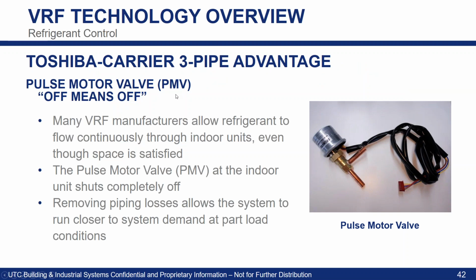So our refrigerant control, exclusive to Toshiba-Carrier. Each fan coil is going to have a PMV valve, or pulse motor valve. And you can see off means off, right? Quotations. There's a purpose why we have that. We are 100% closed on our PMV, okay? So if you guys can envision this, you have a heat recovery system and you have some interior zones that really are not calling for heating and/or cooling. So we don't want any refrigerant traveling through that indoor coil, because if that were the case, we could be overheating or overcooling a space. So that's where our 100% closed PMV can be extremely advantageous, because there are some competitors that don't have that. I'm not going to name any names, but just remember, Toshiba-Carrier is 100% closed. So you don't run into that nuisance call or anything like that.